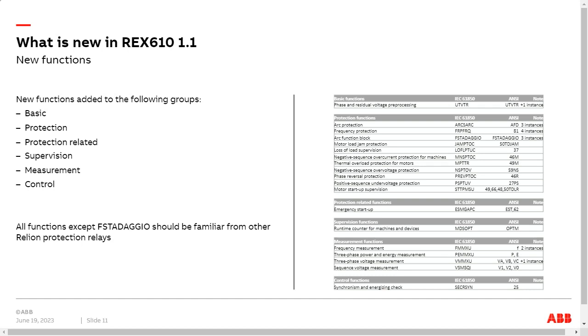Then if you start going through the protection functions from the top, of course there is arc protection, 3 instances because there are 3 sensors, and then there's also this arc function block. That is the only one which should be new to you if you are familiar with the other Relion devices. At least this arc function block is something new, and I will explain about it later on some upcoming slides. Now we also have the frequency protection, and then after that we get a bunch of these motor protection functions.